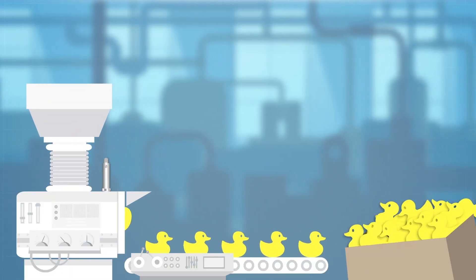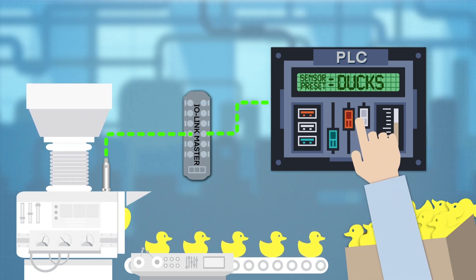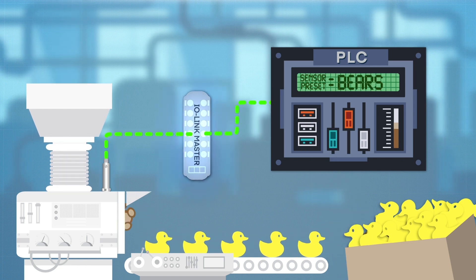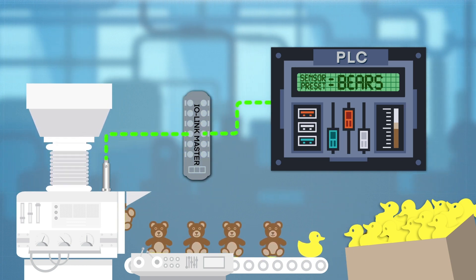For example, if a manufacturer is producing two different products on the same line and needs to change sensor settings between processes, by storing sensor-specific parameter sets in the PLC and then sending them out through the IO-Link master to the sensors, major downtime can be eliminated because there's no need to pull each sensor and reconfigure them manually.